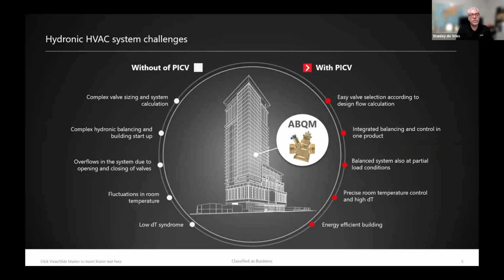All in all, the PICV gives you an easy, foolproof way to always get the right temperatures in the building, but also the right differential temperatures. The efficiency of everything in the building is basically dependent on how much of the energy you're actually pumping into the building, whether cooling or heating, and how much you actually use. Chillers tend to be more efficient with better delta T's, and the same goes for boilers. By also reducing pumping energy, you will get a very energy efficient building, and all the capital equipment in the building will run at its most efficient.